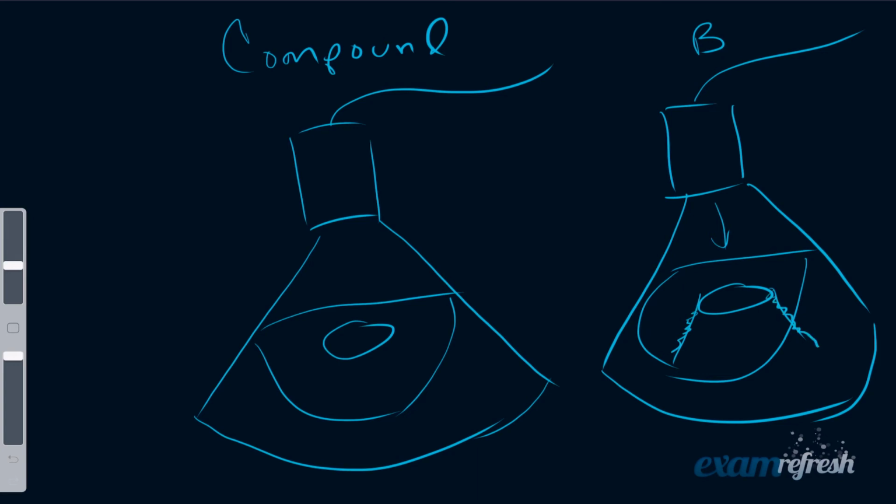So imagine we have another smaller mass hiding back in there where that shadow is. With just general B-mode, one angle of insonation, we won't see that. But with the compound image, what can happen is we can look in multiple angles and basically look around the corner of that mass and see what's hiding back there. So the compound image can reduce that shadow artifact.